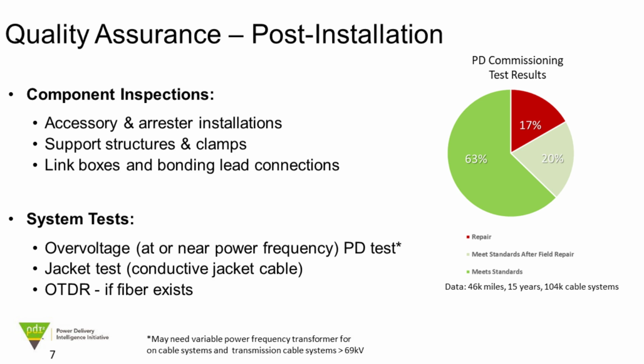And to reiterate this point, I mentioned the most challenging operational issue is voltage transients for cable systems. But the biggest, if we look at the statistics of what causes cable systems to fail, it's primarily the human element. Maybe to a small degree, there are some manufacturing issues, but the vast majority, well over 95% here, are installation, human handling, and that little graph to the right-hand side shows that.